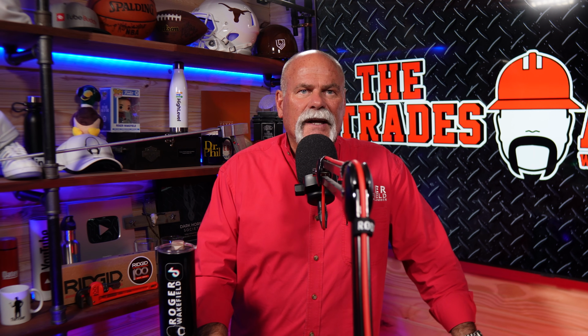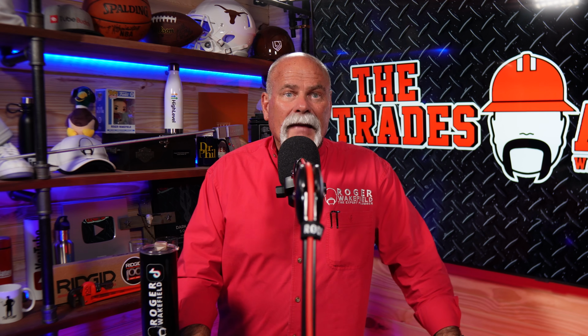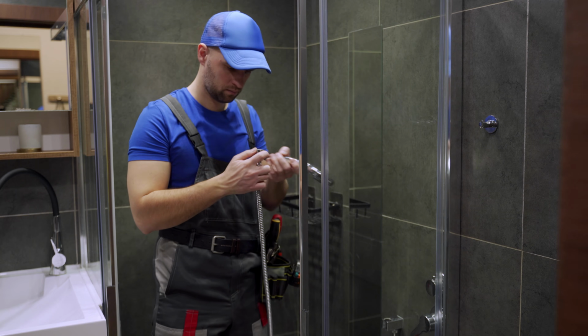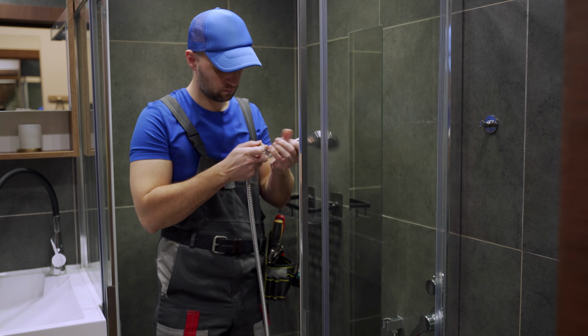I actually talked to some plumbers just the other day at a trade show, and they told me, they said, Roger, you know, we saw your video about that, but we saw it too late. We had actually done a major repipe, did it all in PEX, and they used the exact same PEX size and fittings that they would have in copper, the same size they took out. And they told me, they said, literally, all the showers now have almost no water pressure. And I said, no, you've got pressure, but you don't have the volume.